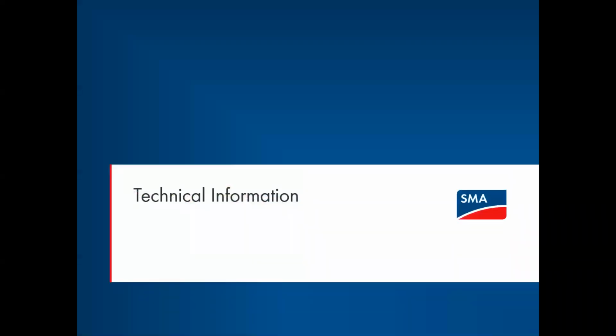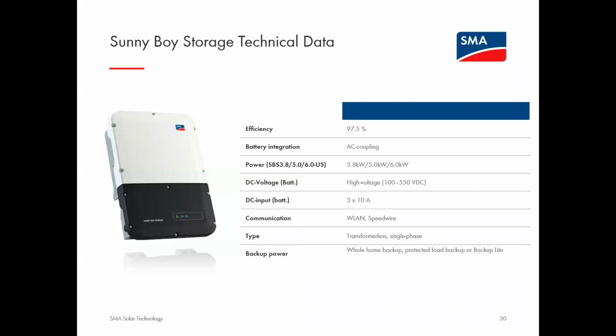All right, so let's jump into a little bit of the technical specs on these products. Again, the SunnyBoy Storage is the core product within the SMA energy storage offering. We've built the SunnyBoy Storage on the same topology as our SunnyBoy PV inverter, and in doing so, we've carried over some of the cool features like the one I was telling you about, the Backup Lite capability. It is an extremely high efficiency inverter, about 97.5%. So even though it is an AC coupled solution, the efficiency losses are quite minimal, even though there is an additional conversion step with an AC coupled system.